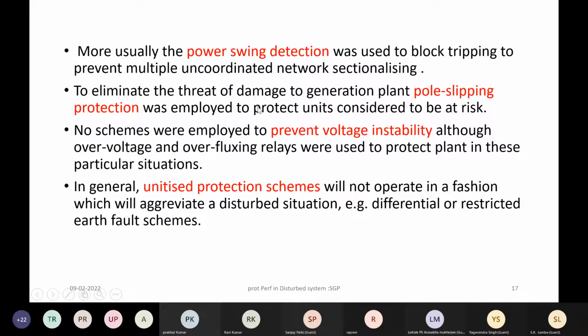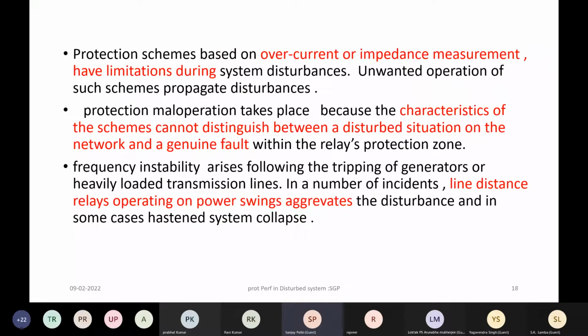Similarly, for damage to the generator, if the power swing is not arrested on the grid side, then the electrical center will move towards the generating plant. And in that case, if pole slipping takes place, then it is risky for the generating station. So the power swing detection and tripping has to be coordinated with the pole slip protection. It should not happen that we have blocked the tripping on power swing on the line, and the swing moves towards the generator and the generator trips. Otherwise, again, loss of generation will result in the collapse of the grid.